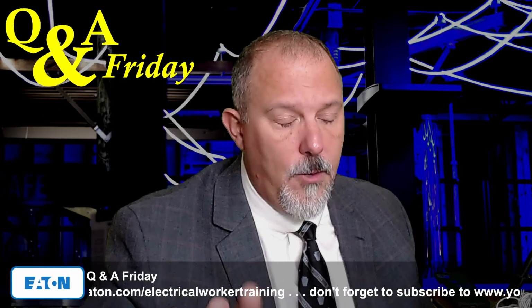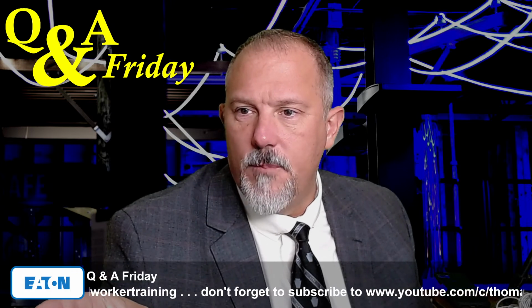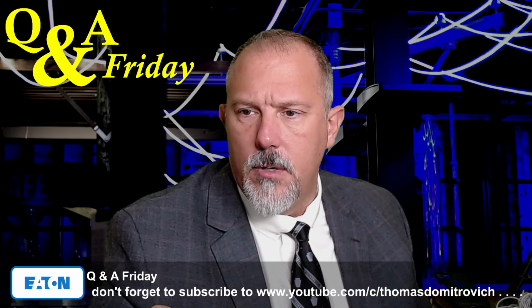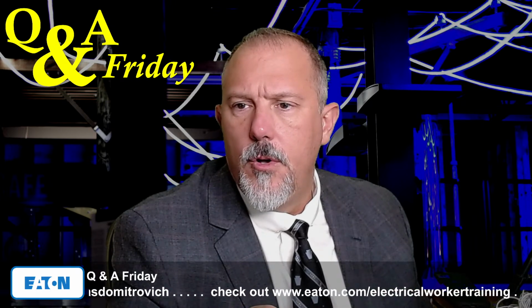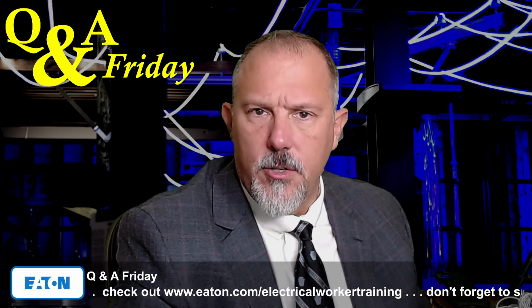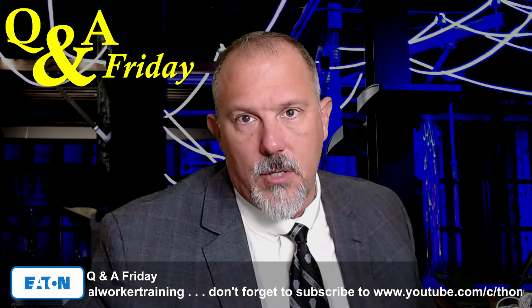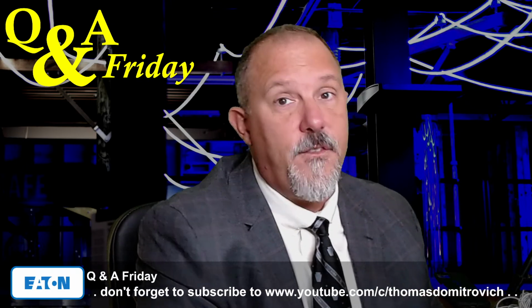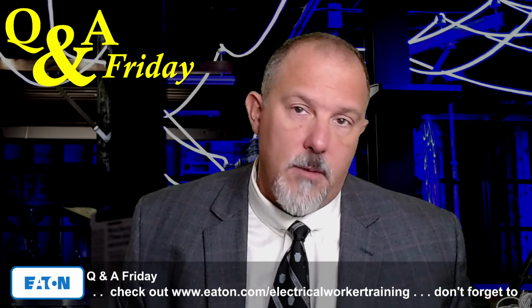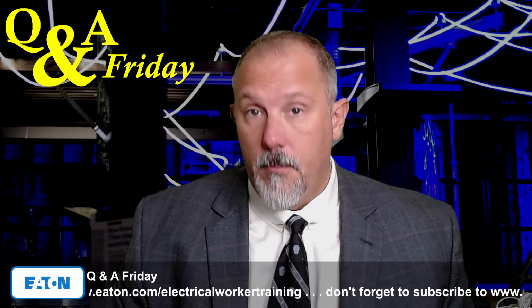So anyway, I believe the language in the code calls for protection of the branch circuit, AFCI, GFCI. Doesn't the branch circuit originate in a panel board? So a regular MCCB and GFCI receptacle doesn't quite cover the entire branch circuit. Right. No, you have a branch circuit requirement to protect the entire branch circuit for AFCIs. GFCIs can be located either in the breaker or in the receptacle. If you put it in the breaker, you're providing AF and GF for the entire circuit. But if you look at the requirements in 210.8(A) or (B), it doesn't mean you have to have it in the breaker and protect the entire branch circuit for GFCIs. So you could have an AFCI breaker in the panel board and a GFCI receptacle. That would be permitted per the code.